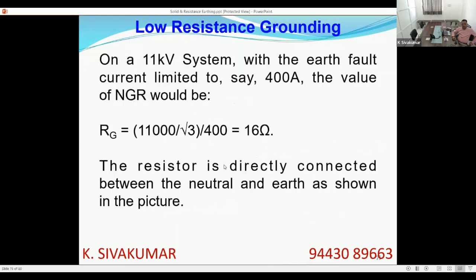So on an 11 kV system, suppose I want to limit the earth fault current to 400 ampere. So 11 kV by root 3, 6.35 kV, divided by 400. I have to connect a 16 ohm resistor. Voltage rating will be 6.35 kV, 16 ohm resistor directly connected across the neutral to ground path like this.